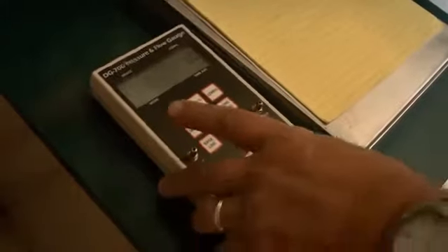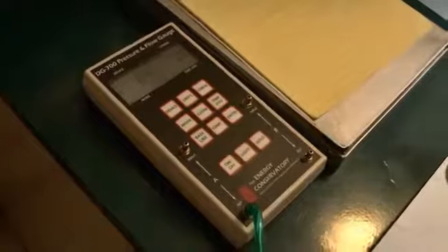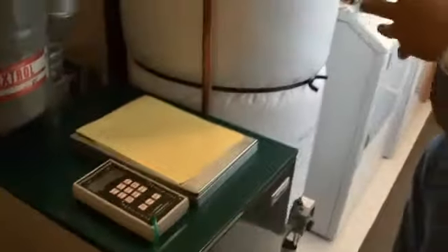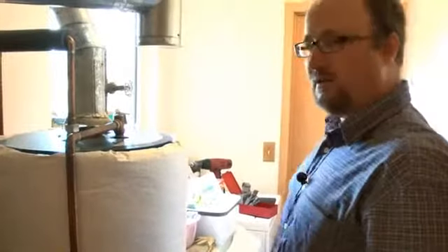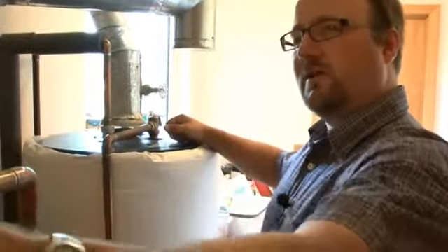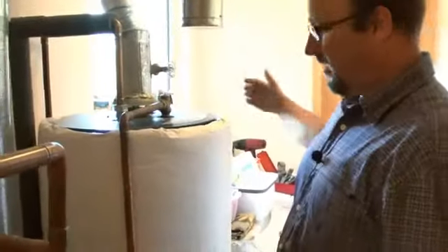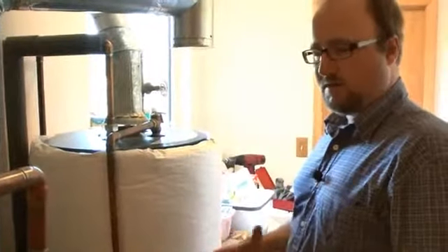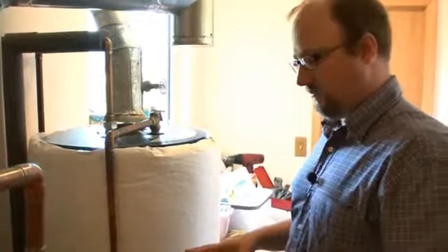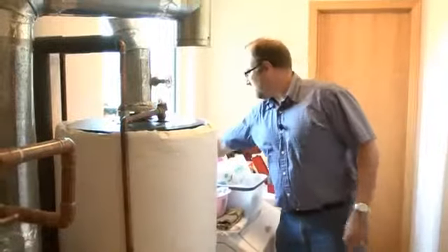Okay, now at this point, based on this being a small room, small area, we'll have this door shut. We'll have the door back here shut. We're going to turn on this bathroom exhaust fan. We're going to turn on the dryer, and we're going to see what our worst case pressure is with respect to outside in here. Okay, we'll turn on the dryer.